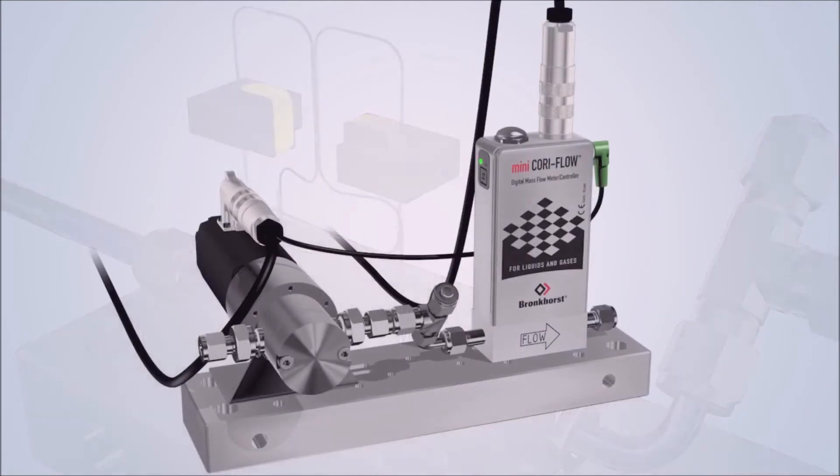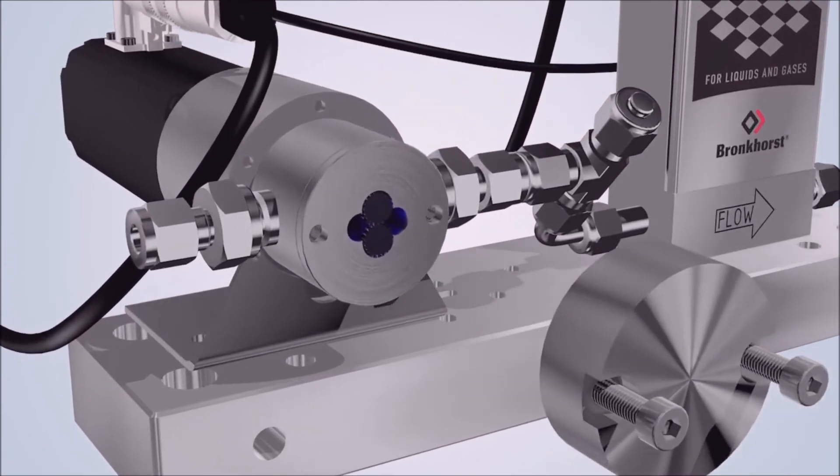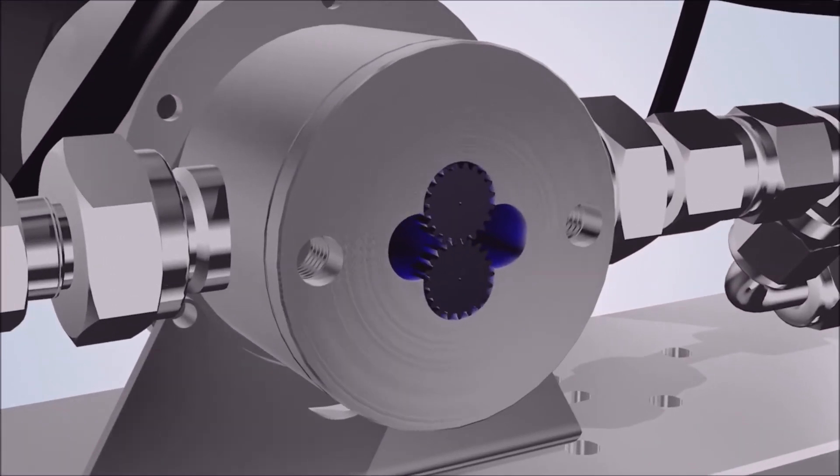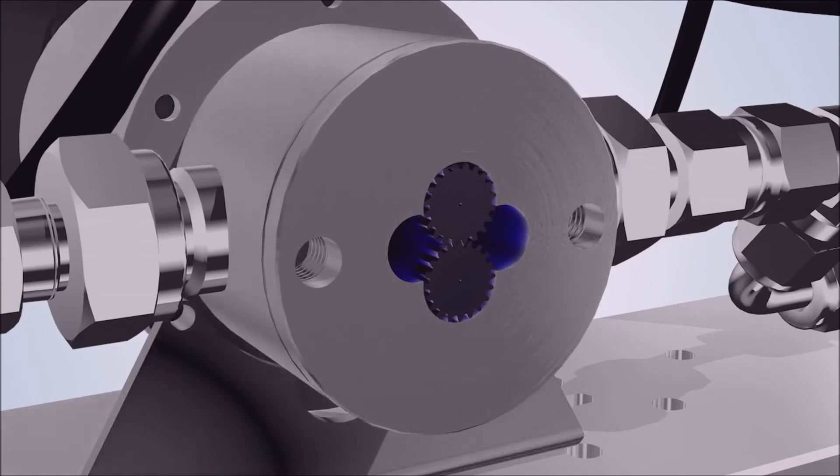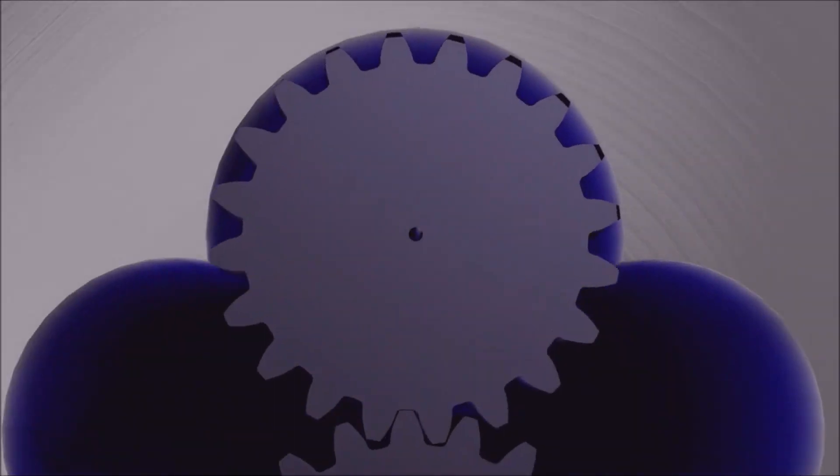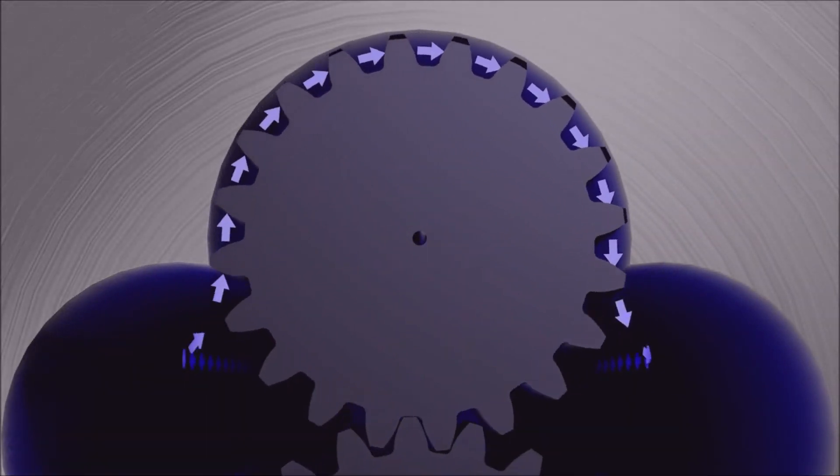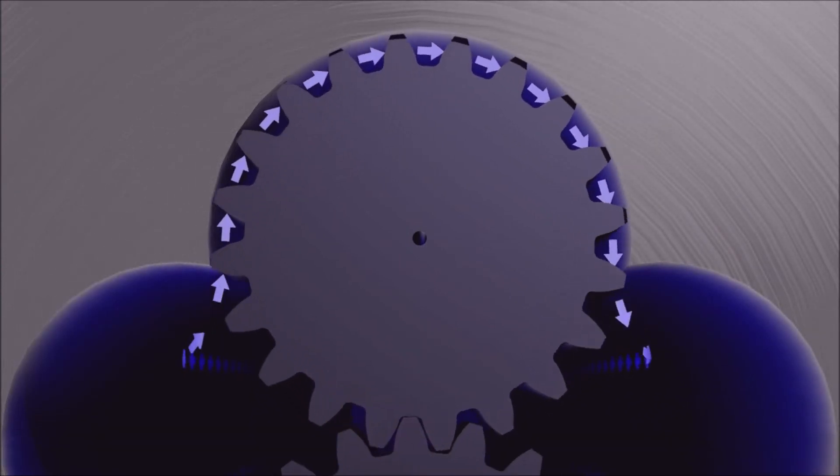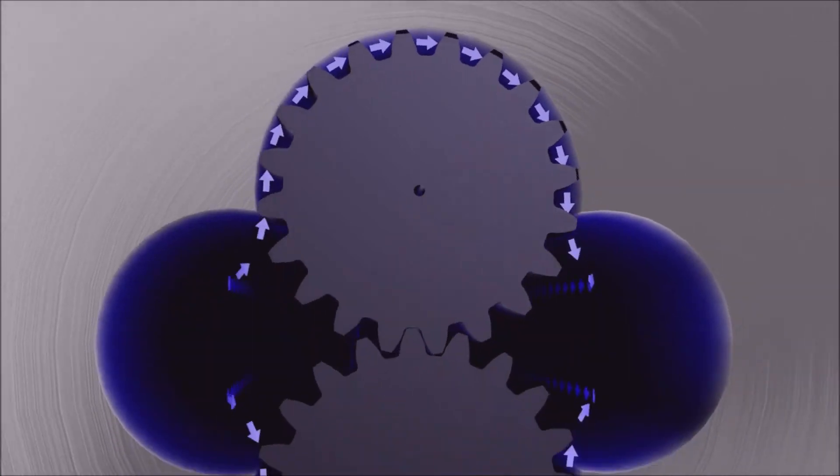The hood of the pump, which is available in stainless steel or Hastelloy, conceals two gears which sit underneath. The space between the cogs is filled with liquid. The speed of the pump depends upon the required flow. The advantage of a gear pump is that it has considerable range.